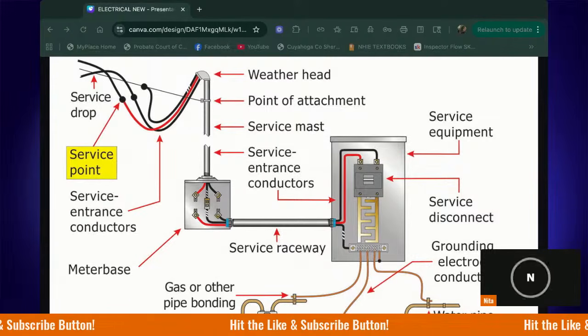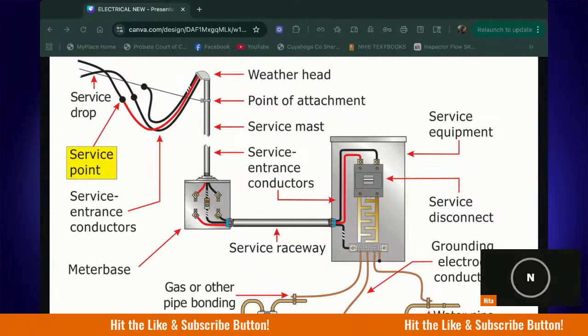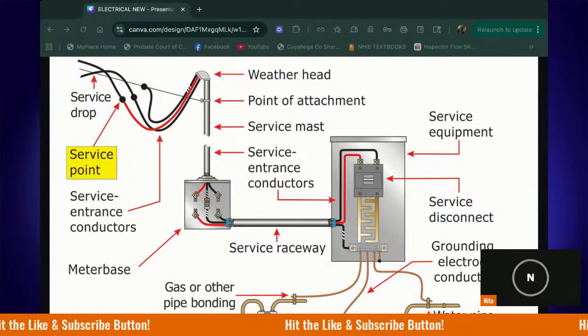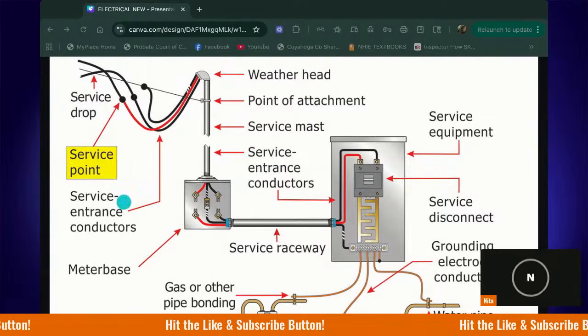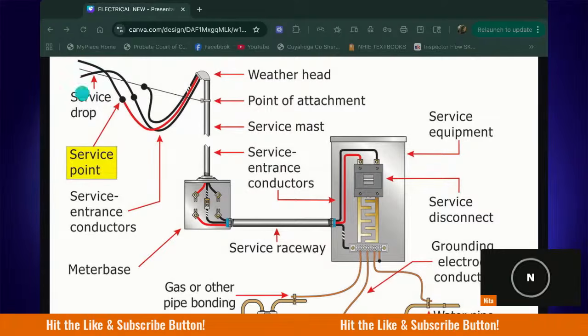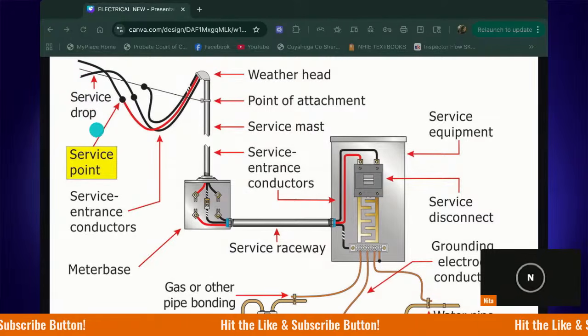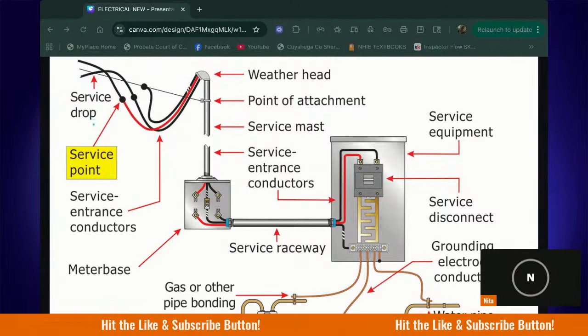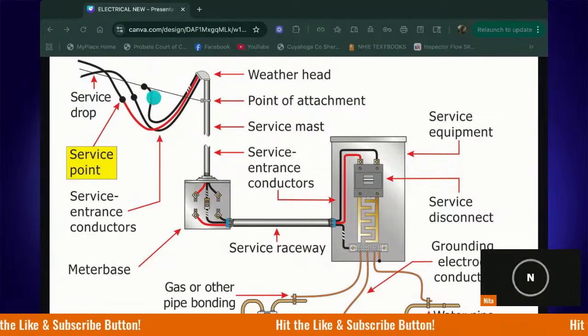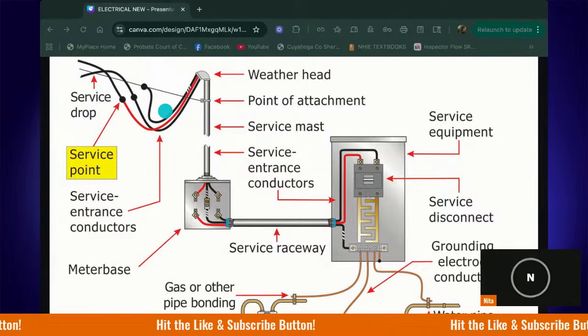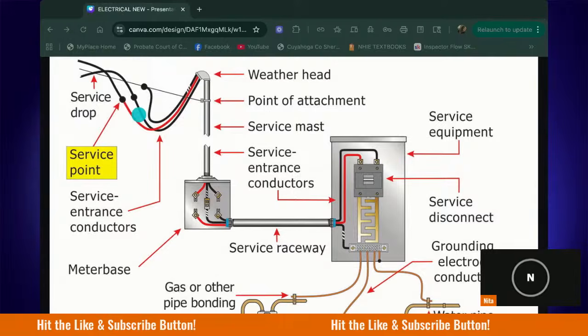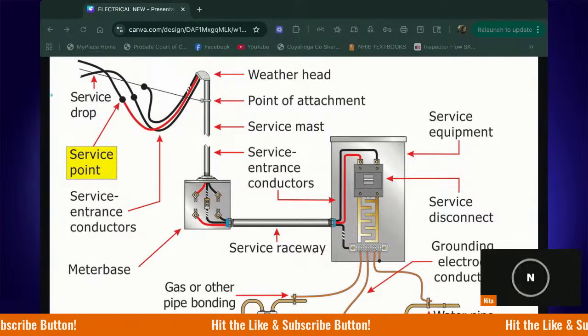Step 4. After the service point, the wires become the service entrance conductors. You see here, they are service drop. They're dropping down from the transformer. They splice or connect with these service entrance conductors. These are the conductors that will be entering the house.